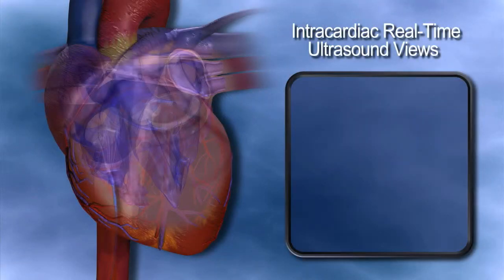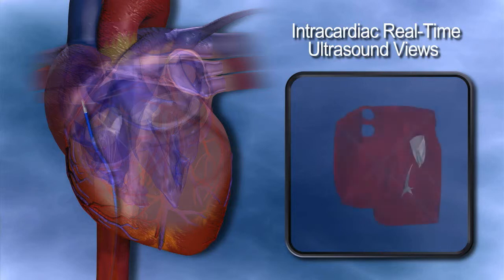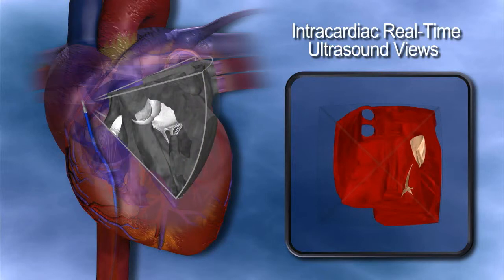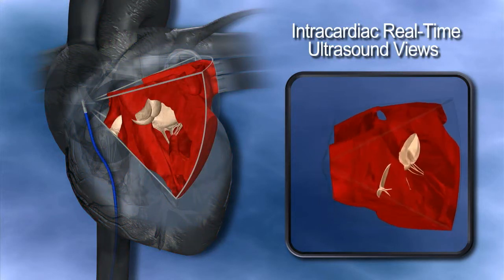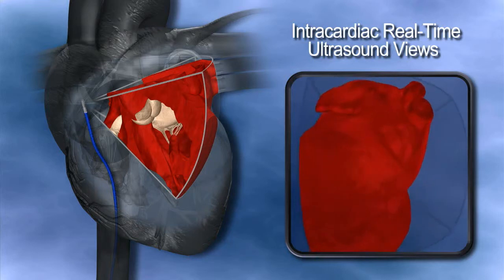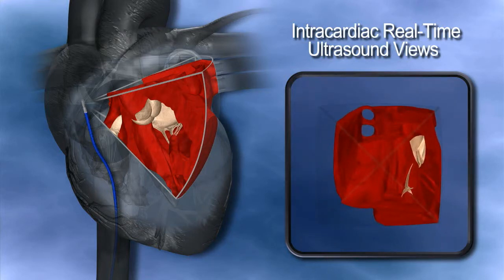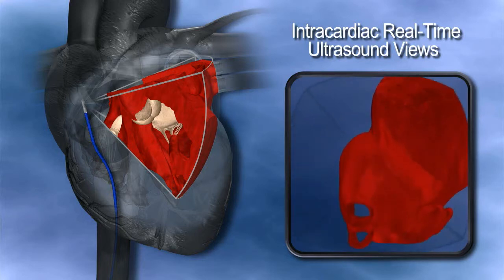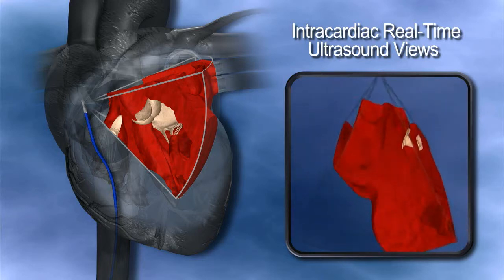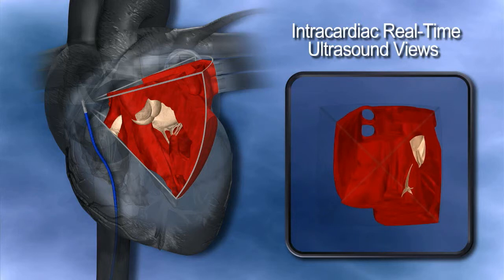The ultrasound catheter would be placed in the right atrium and positioned to point at the target — which might be a mitral valve, aortic valve, or the pulmonary veins. It produces a pyramidal shape view instantaneously while the heart is beating. That image can be manipulated by rotating the volume, cutting into it at any arbitrary angle, and rotating a plane or any image within the volume in real-time — all without having to reposition the catheter.